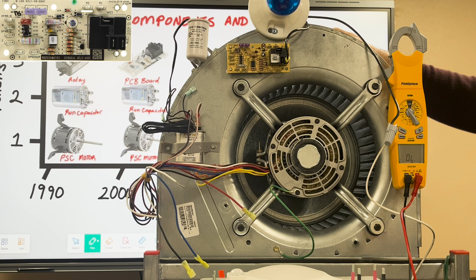We're over at the blower motor now. We've got a blue light bulb and the PCB board, and we already have the light hooked up to the board. This is hooked up to the normally closed terminal, just to show you there's always power here if the relay is in the open position for the normally closed, which is the practical way of wiring the motor. So if the motor's off, there's always power on this terminal. We wanted to demonstrate that so you always know it, instead of hooking something up to it and wondering what's going on.